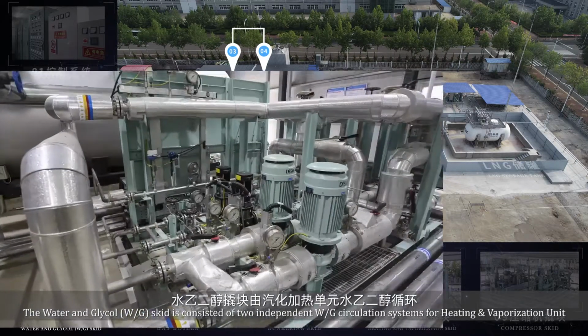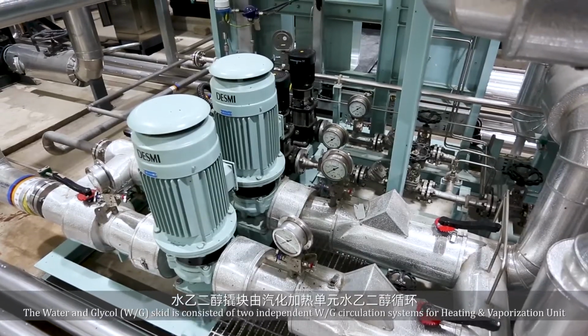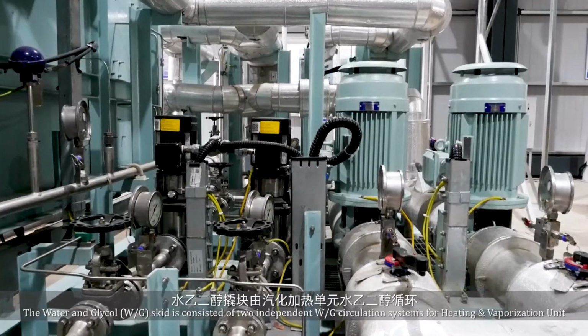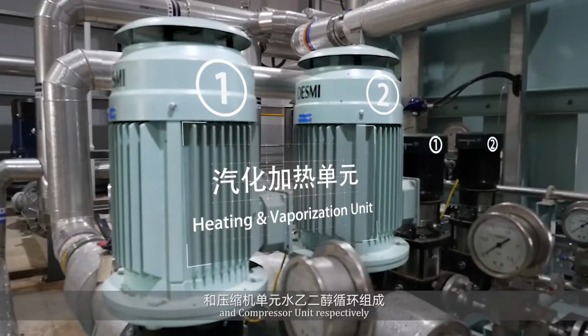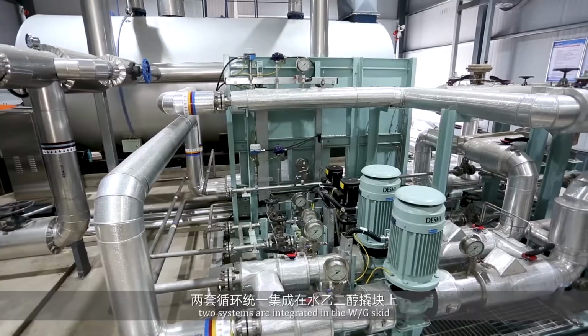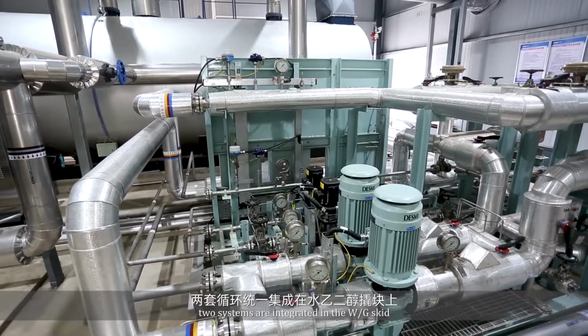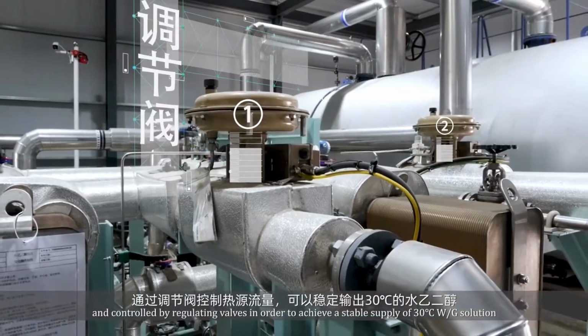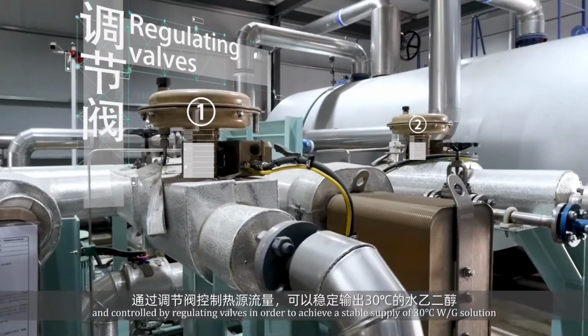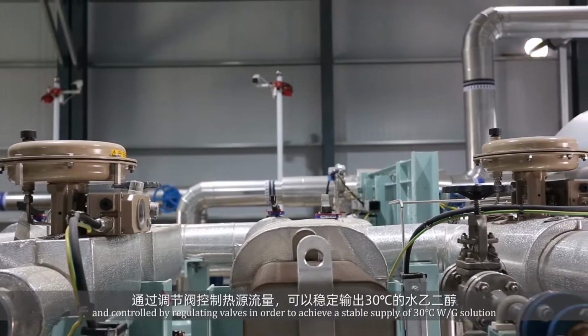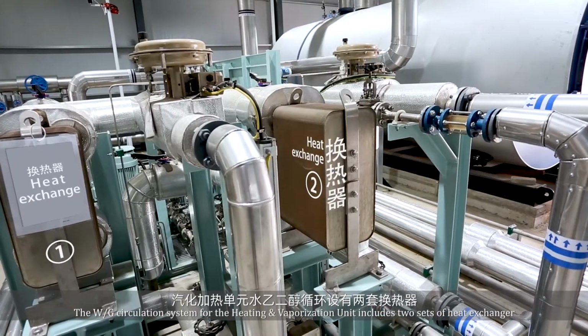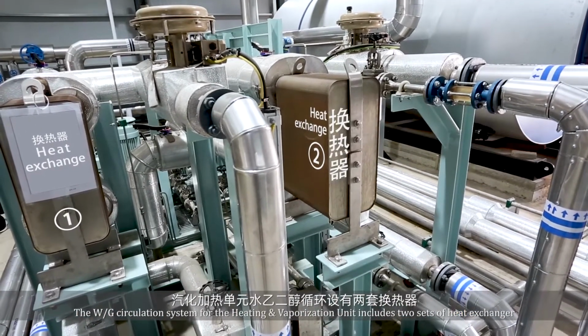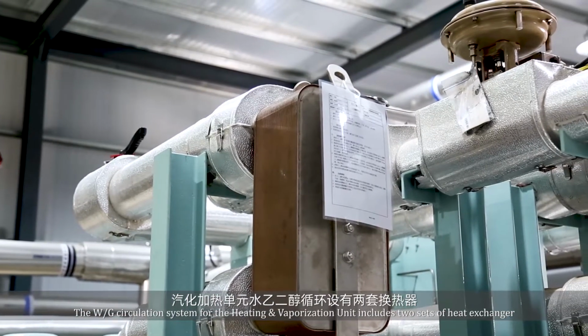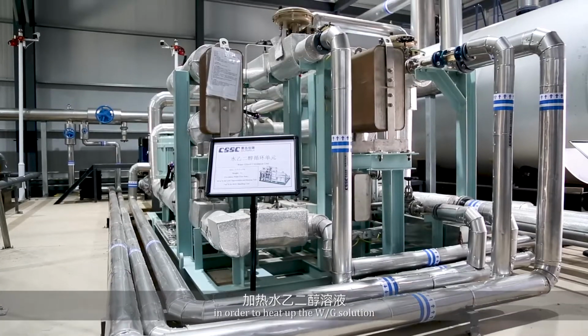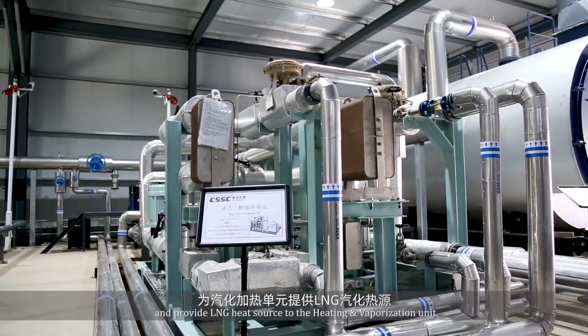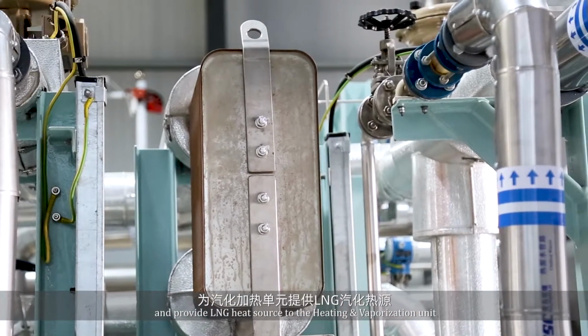The water and glycol skid consists of 2 independent WG circulation systems, for the heating and vaporization unit and the compressor unit respectively. The 2 systems are integrated in the WG skid and controlled by regulating valves in order to achieve a stable supply of 30 degrees WG solution. The WG circulation system for the heating and vaporization unit includes 2 sets of heat exchangers in order to heat up the WG solution and provide LNG heat source to the heating and vaporization unit.